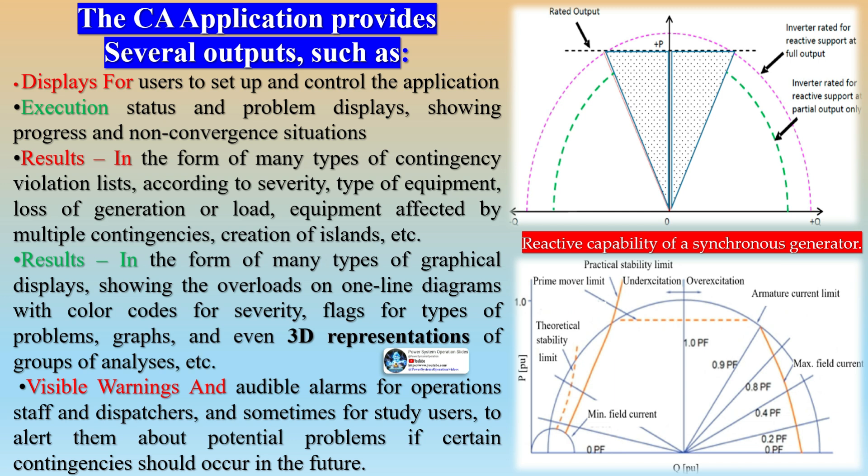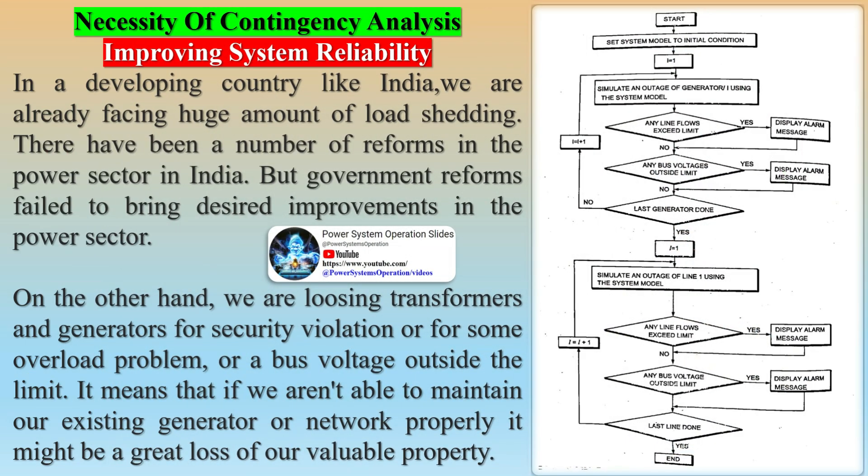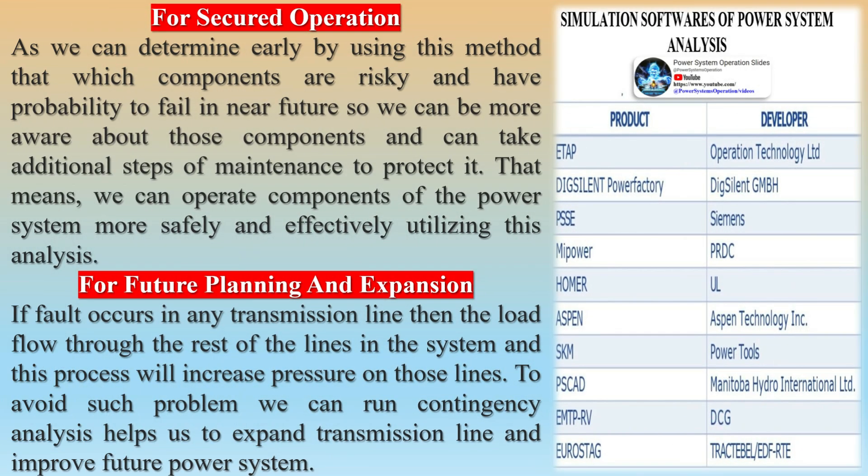Contingency creation, selection, and evaluation are the three main divisions of contingency analysis. Many studies have focused on contingency selection with the goal of reducing the extensive list of contingencies by choosing those outages with serious limit violations. The individual outages are then evaluated using load flow, and the activity continues until there are no post-contingency violations. Contingency creation is the first stage of the contingency analysis process.